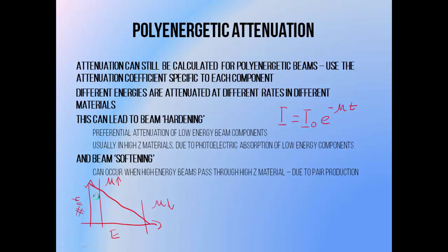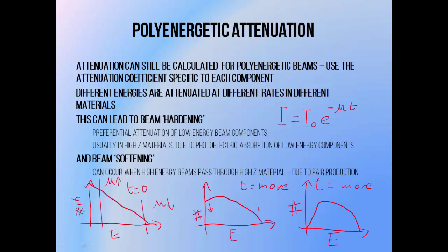Consider a spectrum that still has a lot of low-energy components — before passing through any material. Once the beam has passed through a little bit of material, the low-energy part of the spectrum decreases relative to the high-energy part, because the lower-energy part has a higher linear attenuation coefficient. The lower-energy part of the spectrum is being filtered out. As the beam passes through more material, the lower-energy components are attenuated more and more. This process is known as beam hardening — the preferential attenuation of low-energy beam components.